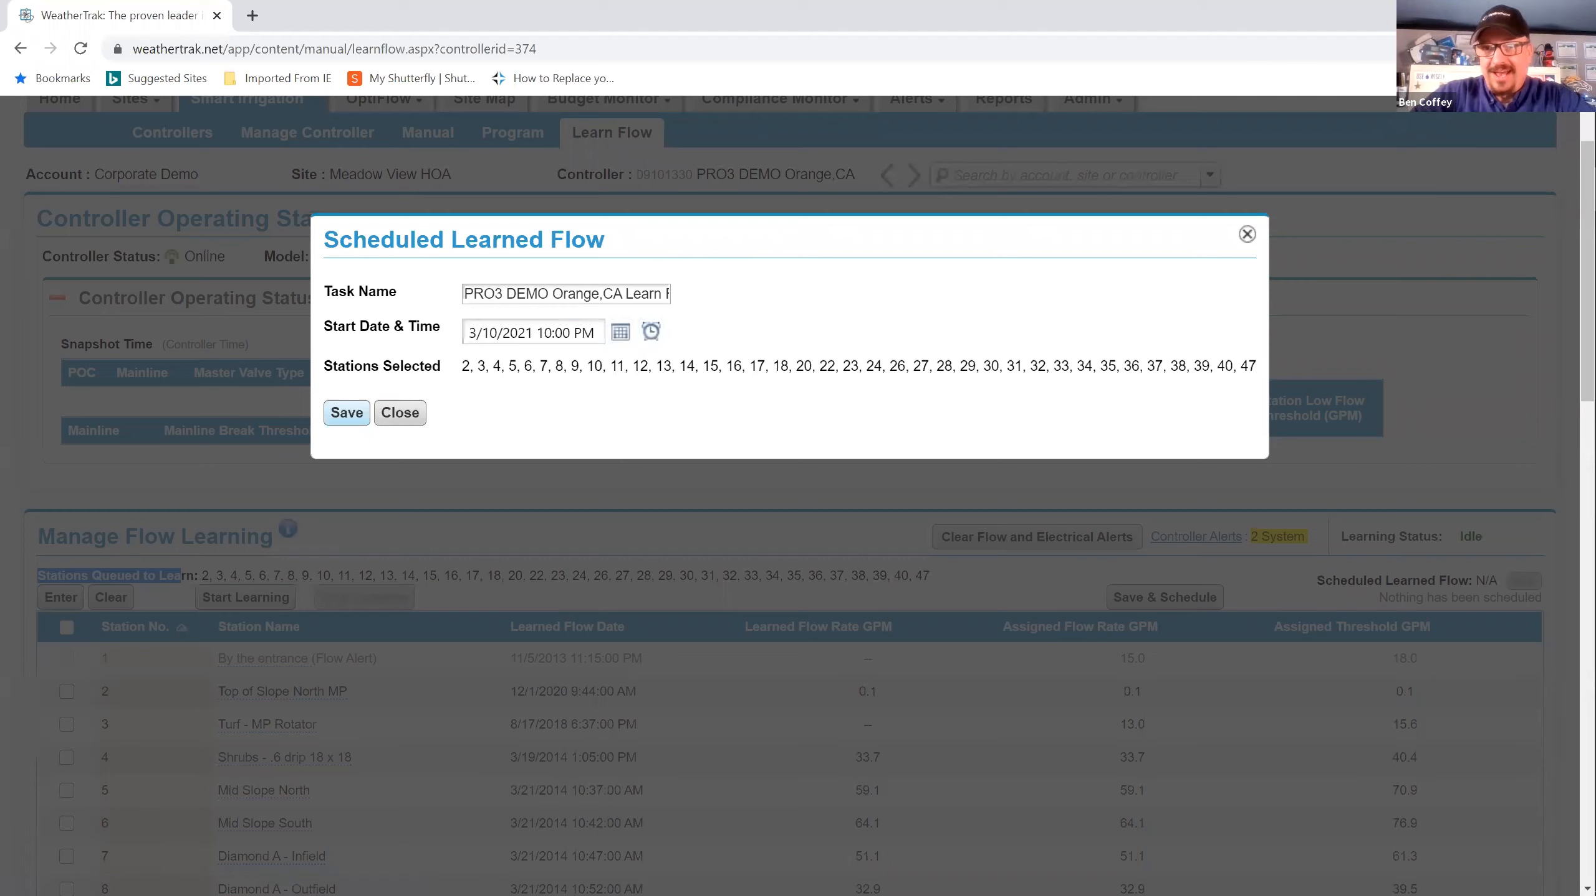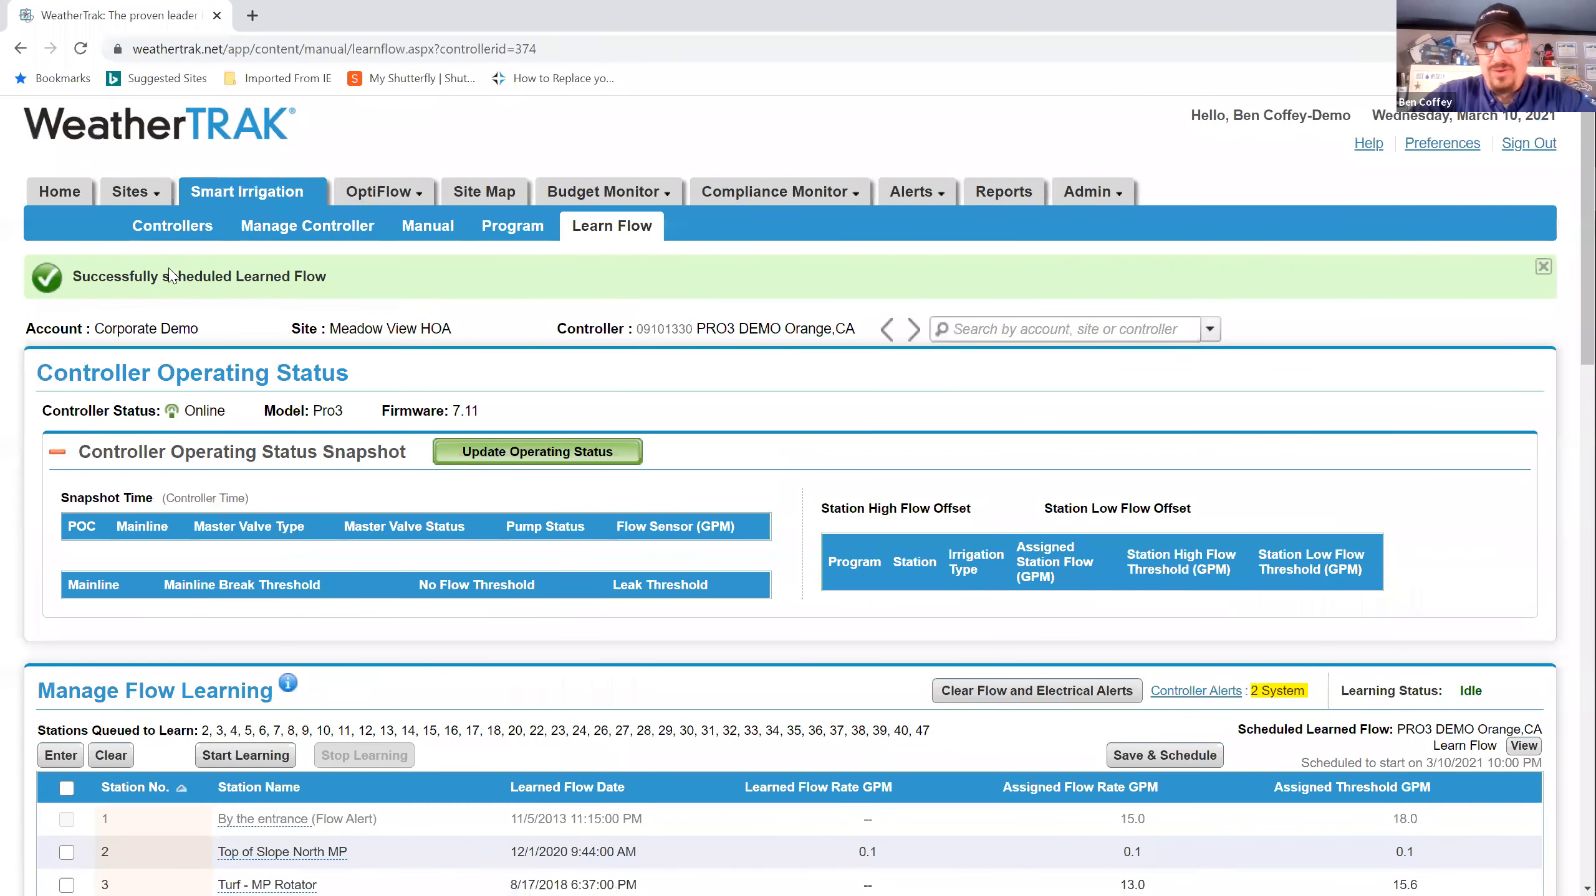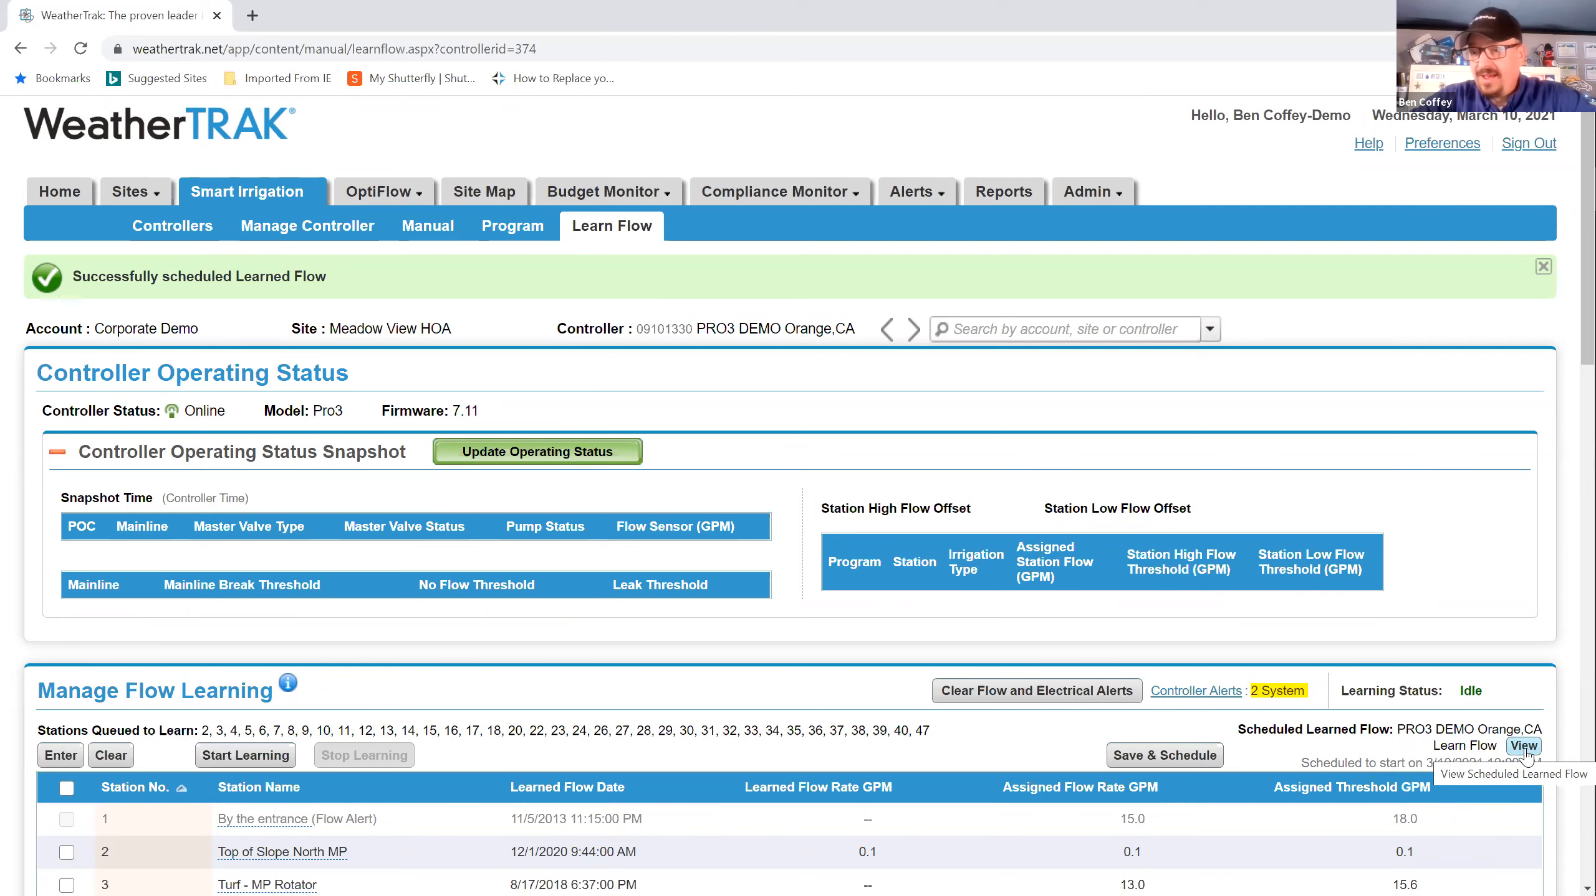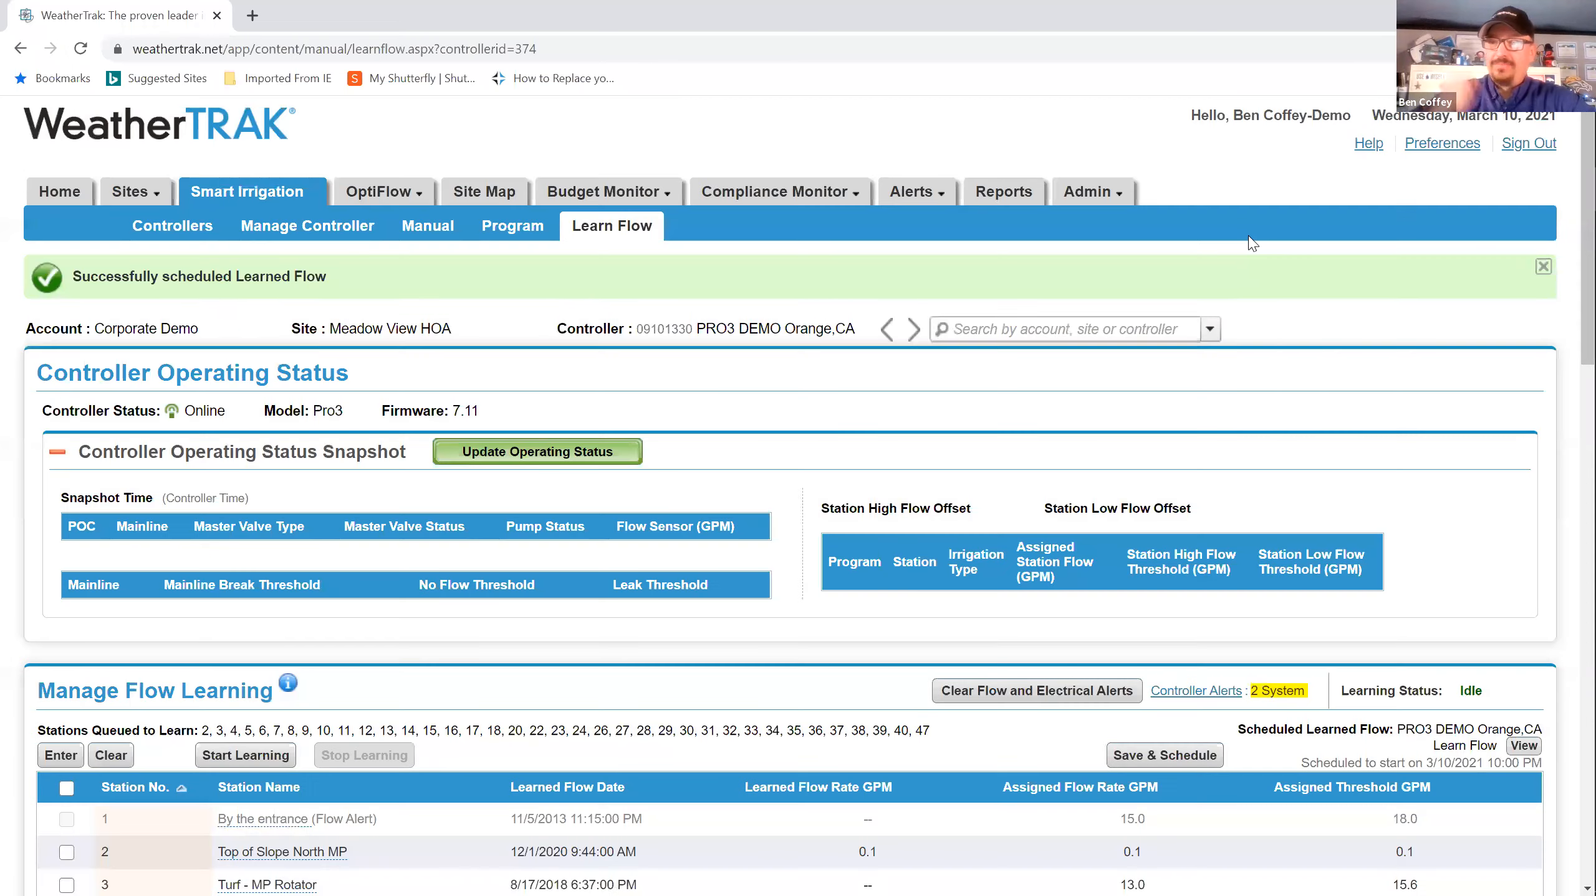I especially like it for OptiFlow applications. Because sometimes when we implement OptiFlow, we've got other controllers that we need to learn flow on and scheduling it to happen rather than sitting around and doing one and waiting for it to finish and then doing the next one can be a huge time saver. So just know that with OptiFlow, if you're using that application, you might get alerts that push back on you. They won't let you overlap. The OptiFlow system will say controller A is still learning. You can't run controller B yet. So make sure that you know how long your learn flow tests take and how long the system will be busy doing that before you try and schedule multiple controllers.